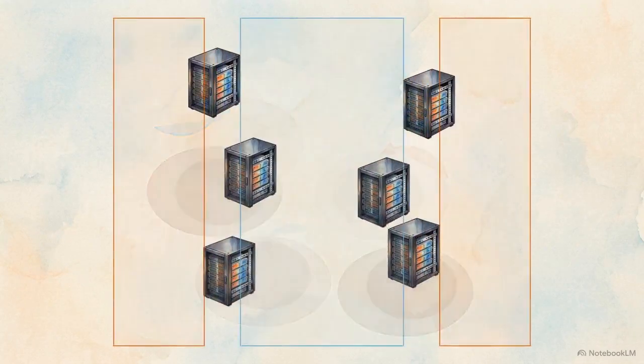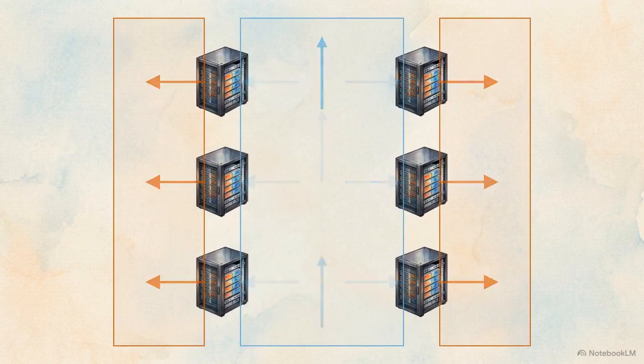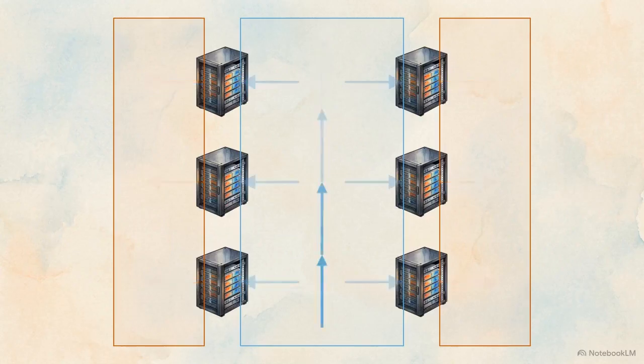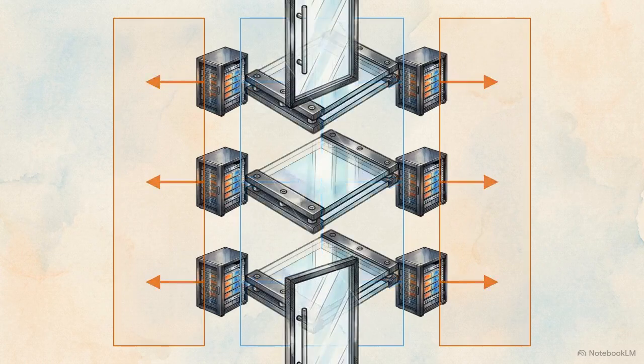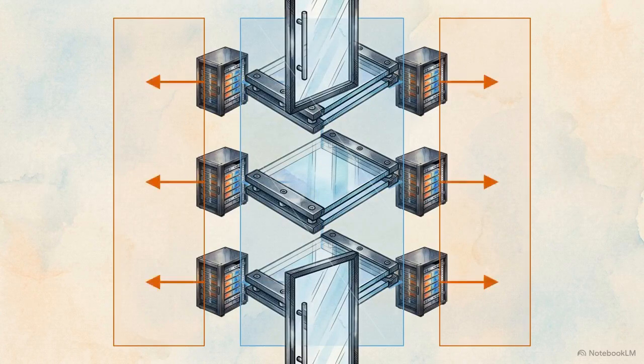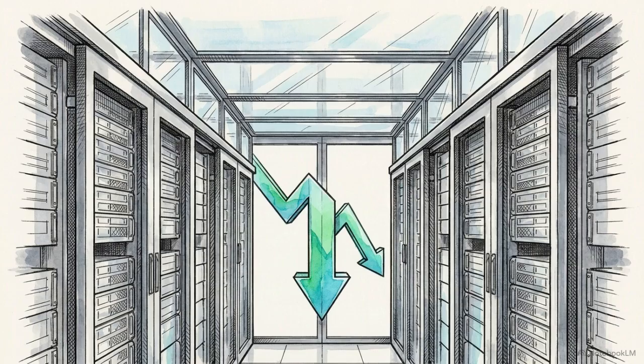First, the server racks are reorganized so that the fronts face inward toward each other. This creates a dedicated central channel strictly for pulling in cold air. Next, the backs of the racks vent outward into opposite aisles, forming a completely separate zone designed exclusively to collect the hot exhaust. Finally, by capping these rows with sliding doors and physical ceilings, the zones are completely sealed off. The hot and cold air loops are physically blocked from ever mixing. By simply manipulating physical space, engineers dramatically drop a facility's overall energy consumption without touching a single piece of the actual cooling machinery.